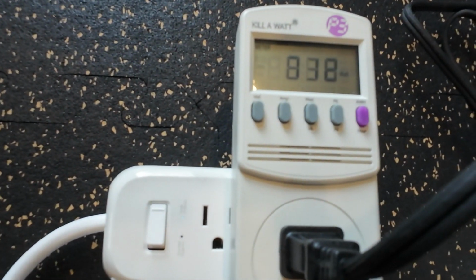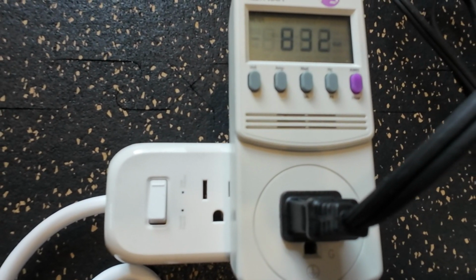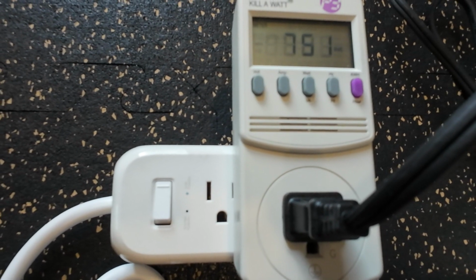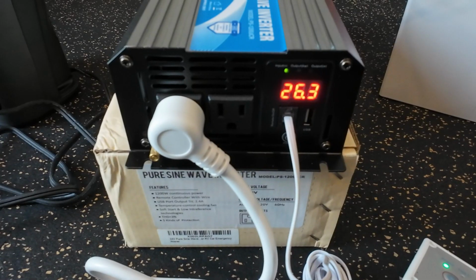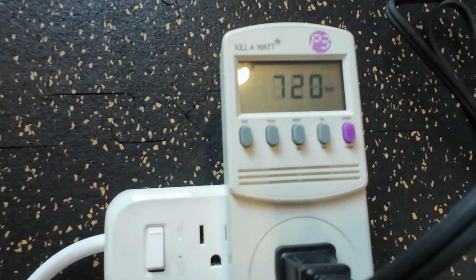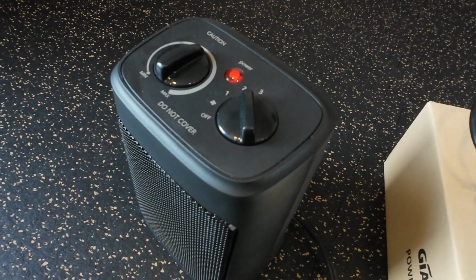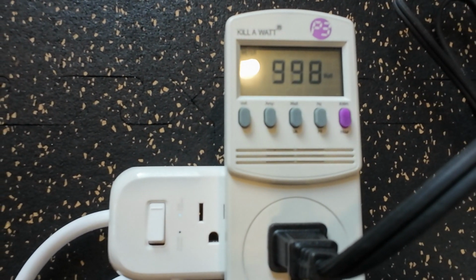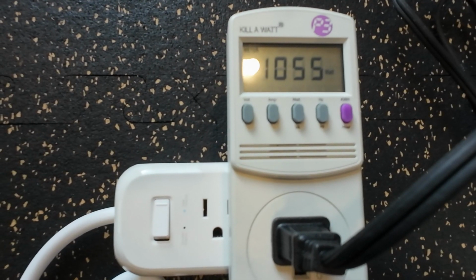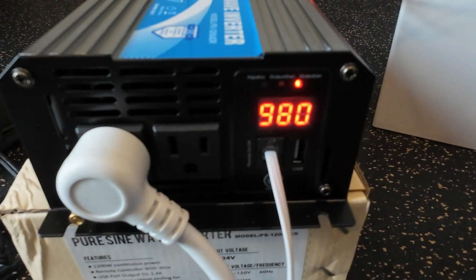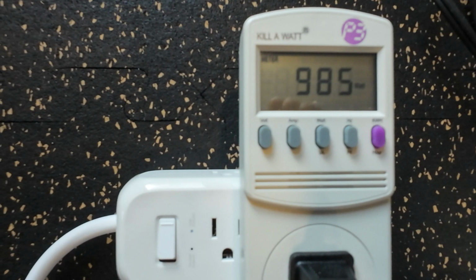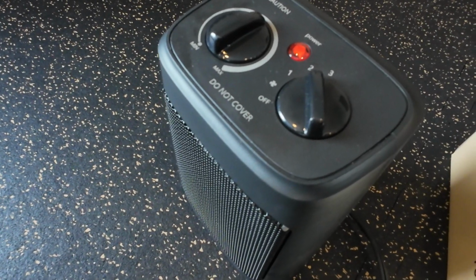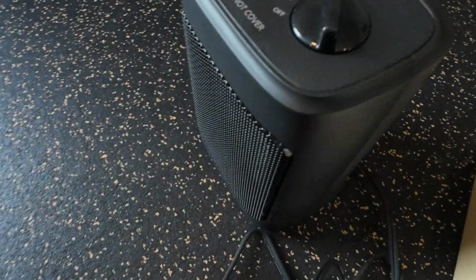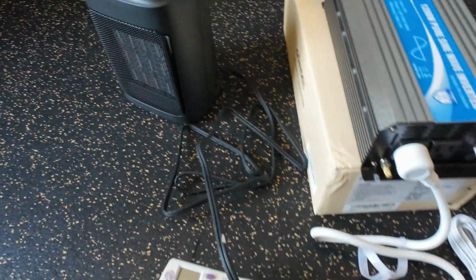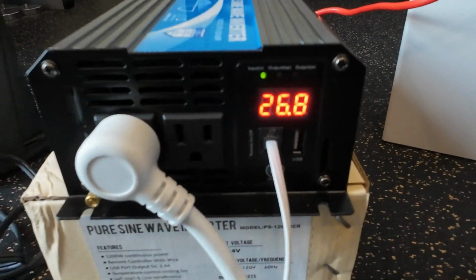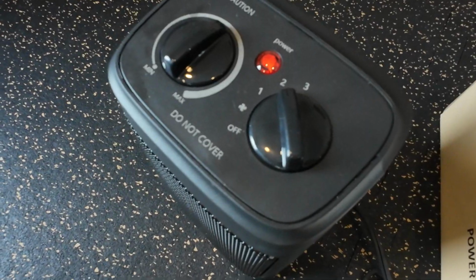At level 1 on the space heater, the power use goes up to 750 watts range. The display on the inverter kind of matches the reading on the Kill A Watt meter. At level 2 of the space heater, the power usage goes up to 1050 watts and then settles around 975 watts. When I turned the heater to level 3, which is 1500 watts power usage, the inverter overloads and stops working, which is expected because inverter's maximum wattage is rated at 1200.